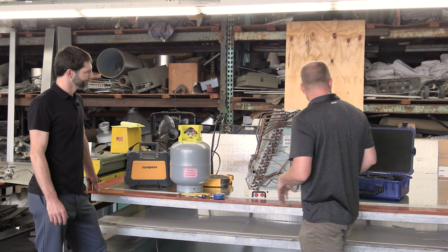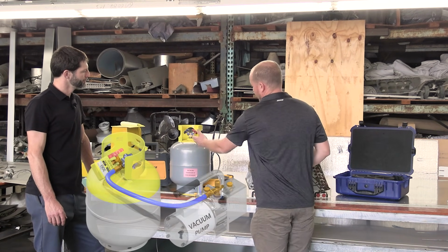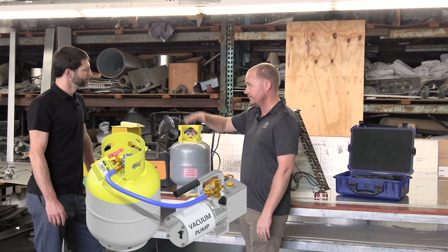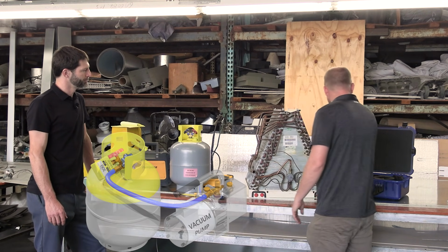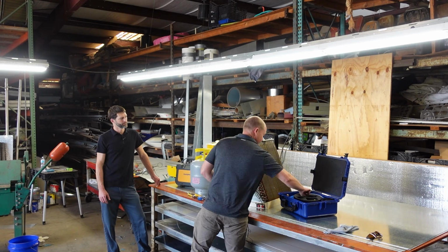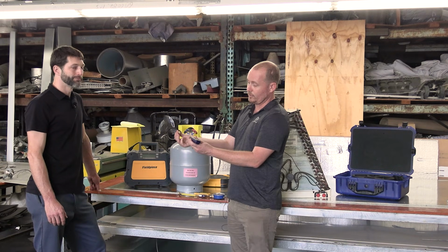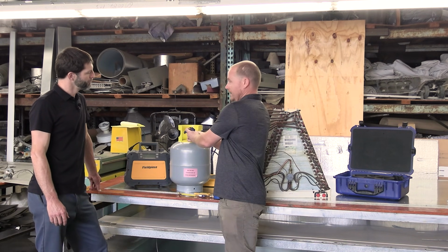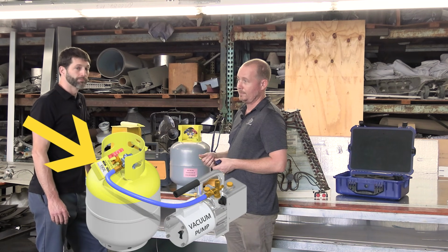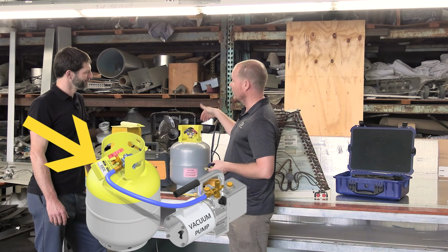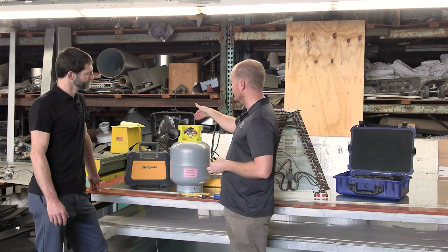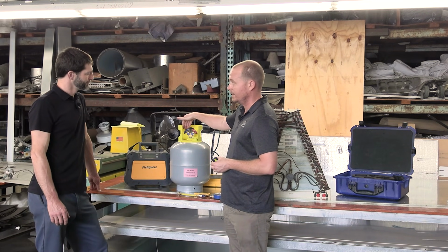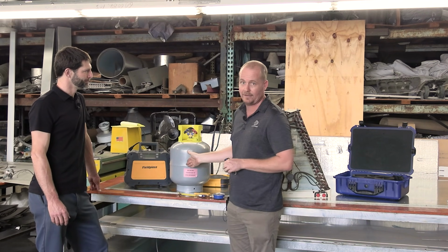It's really easy to do. You just hook a vacuum gauge. Generally, we're going to use a large gauge hose, go from here to the vacuum pump, and then you can literally just hook your micron gauge. You need to have an adapter here. You can just hook your micron gauge with an adapter up to the other side and measure that pressure. Now, generally speaking, if you want to pull a vacuum quickly on a tank, the easier side to do it is on the vapor side because the vapor side doesn't have a dip tube.